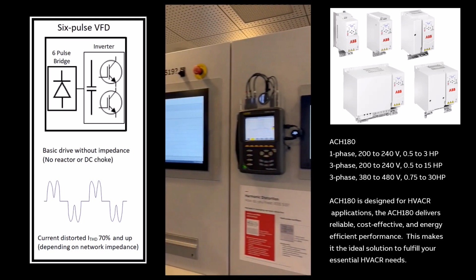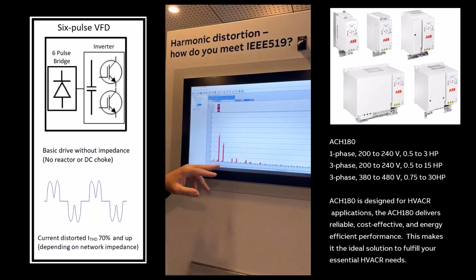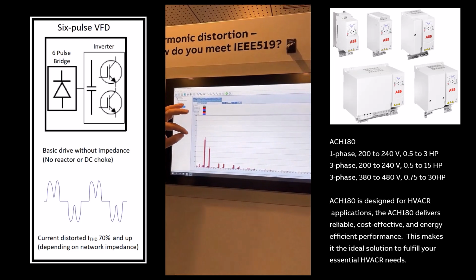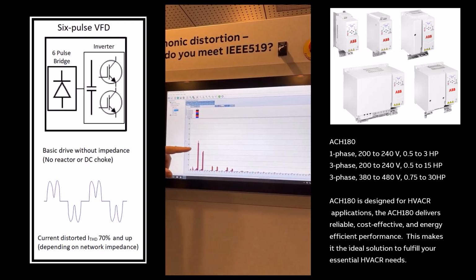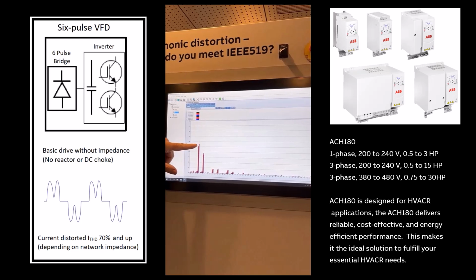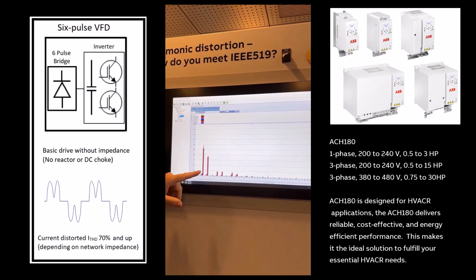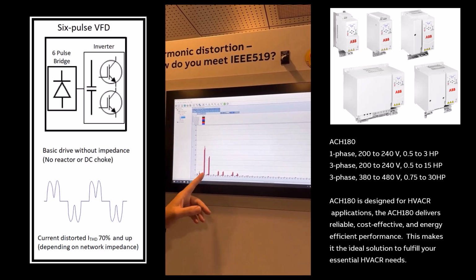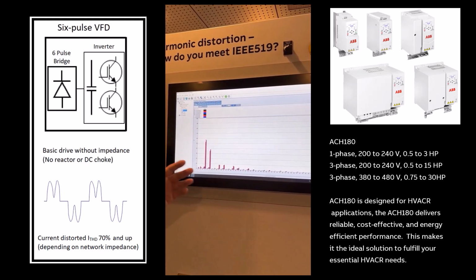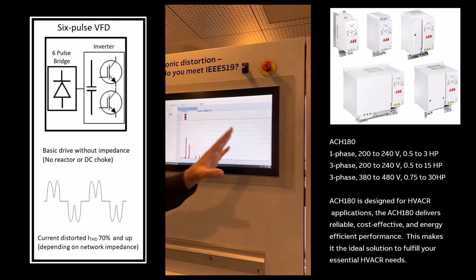If we look at the harmonic schedule here, we see the 5th, the 7th, 11th, and 13th harmonic. Compared to the fundamental, the 5th is showing almost 59% of the fundamental current of 60 hertz, and the 5th is 300 hertz. And each one of these frequencies is a multiple of 60 hertz. So that's the equipment that's set up.